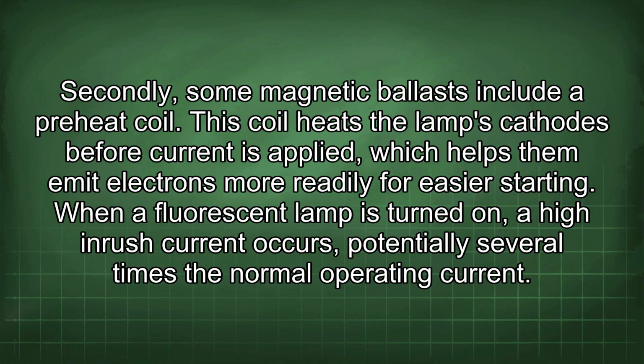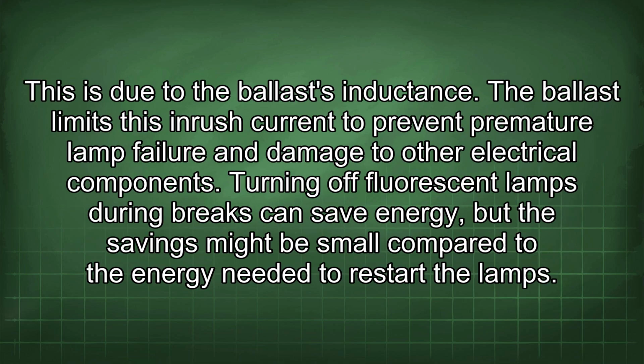Secondly, some magnetic ballasts include a preheat coil. This coil heats the lamp's cathodes before current is applied, which helps them emit electrons more readily for easier starting. When a fluorescent lamp is turned on, a high inrush current occurs, potentially several times the normal operating current. This is due to the ballast inductance. The ballast limits this inrush current to prevent premature lamp failure and damage to other electrical components.